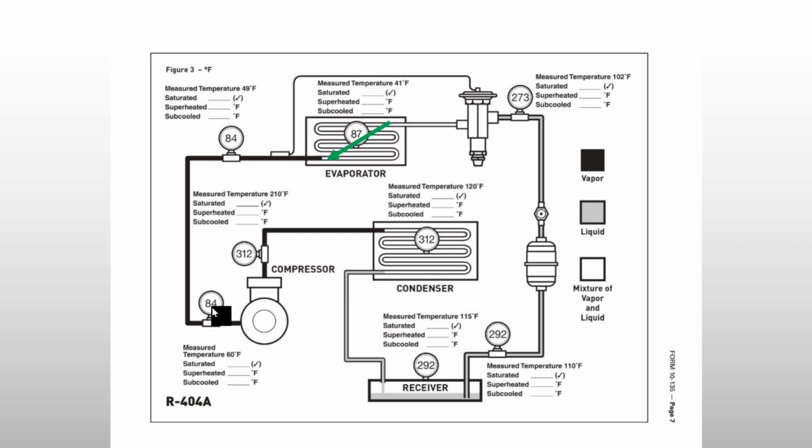What we have in your coil now is a glide. It's also going to have a saturation point where when the refrigerant goes in there, it's going to either boil off or condense at different rates. Remember that the refrigerants are made up of multiple different refrigerants, and each one has its own boiling and condensing point.